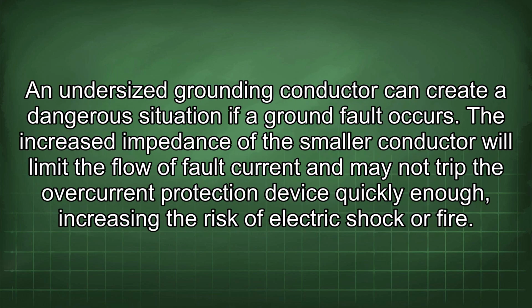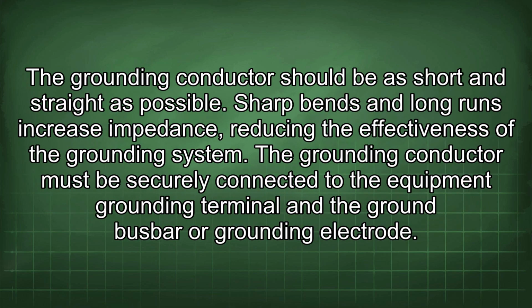An undersized grounding conductor can create a dangerous situation if a ground fault occurs. The increased impedance of the smaller conductor will limit the flow of fault current and may not trip the overcurrent protection device quickly enough, increasing the risk of electric shock or fire. The grounding conductor should be as short and straight as possible. Sharp bends and long runs increase impedance, reducing the effectiveness of the grounding system.